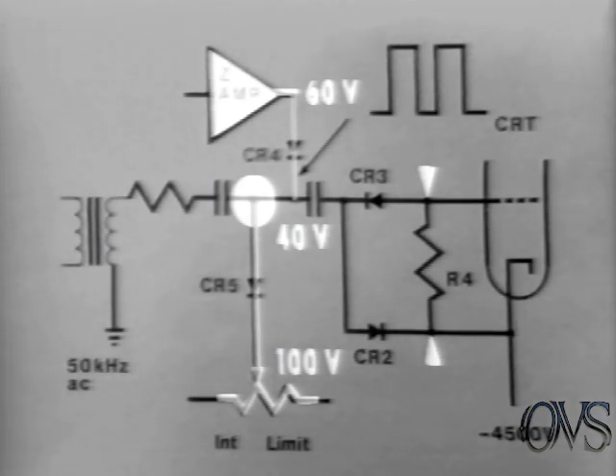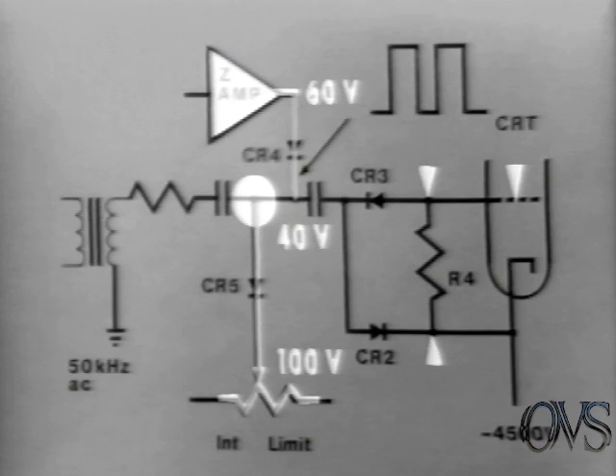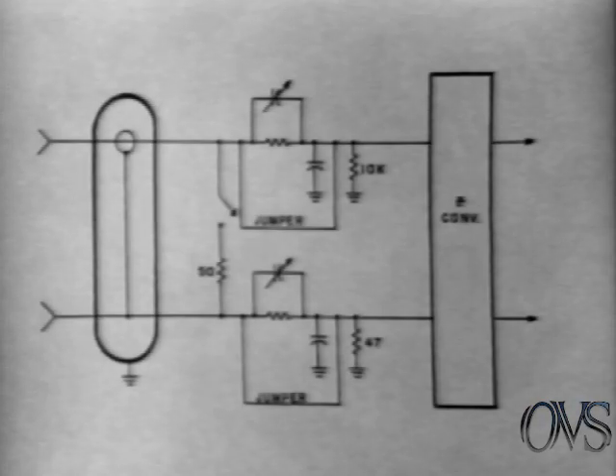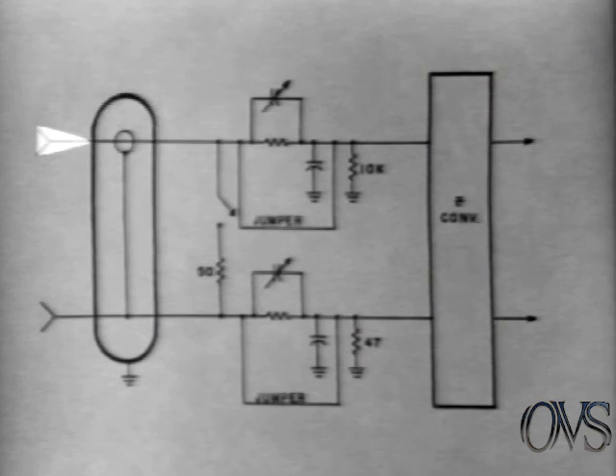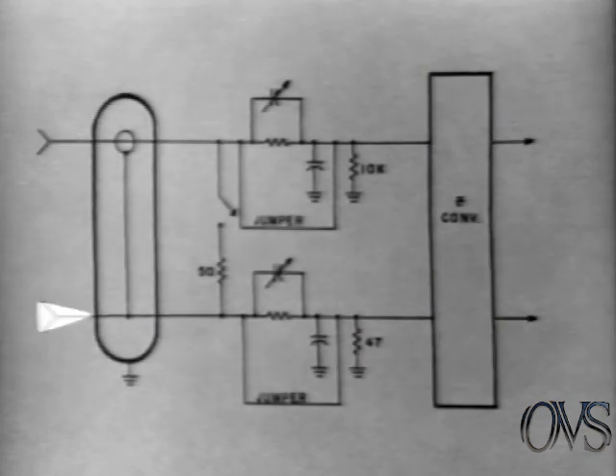Since the grid voltage is always referenced to the fixed cathode potential, the grid will accurately track the output of the Z-axis amplifier. The focus grid circuitry is similar. Next, let's discuss the X and Y axis deflection circuits. The inputs are fully differential. A triaxial cable is used, with a center conductor going to one side of the input, the shield going to the other side, and a grounded shield around both of these.